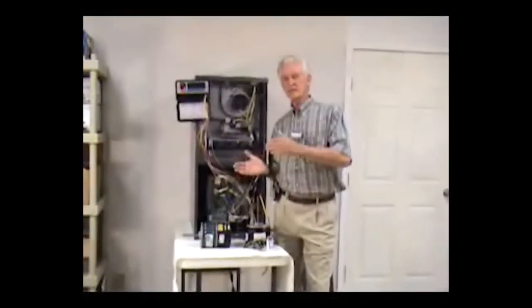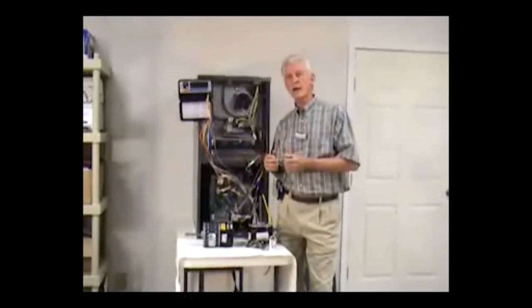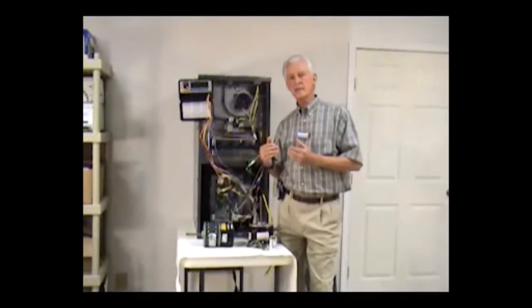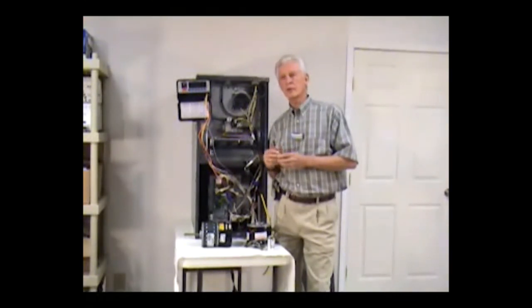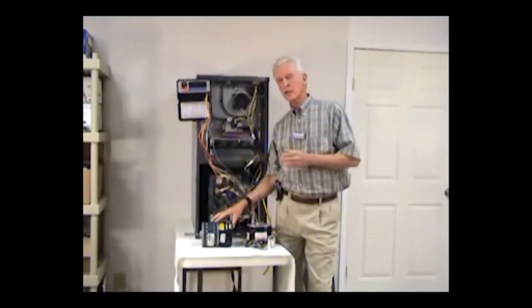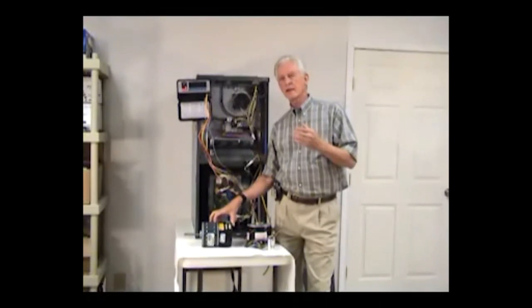What that does is give you this whooshing sound or huffing sound, if you will, and that is an indication that you have probably high external static pressures that you need to look at and deal with so that you can overcome that problem that the motor has. They do not always do this, even under high static ranges. Sometimes what these motors will do will actually back off in their CFM delivery, and then they stay at that range, so you're not really delivering the CFM that is required for the application that you might have.